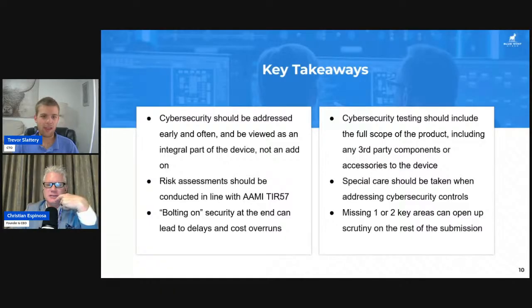Now, penetration testing should be outsourced. The FDA very frequently will request that cybersecurity testing is done by an independent third party, and oftentimes they will require it. As the manufacturer for this product, be sure that you are working with a company specializing and focusing in this medical area.